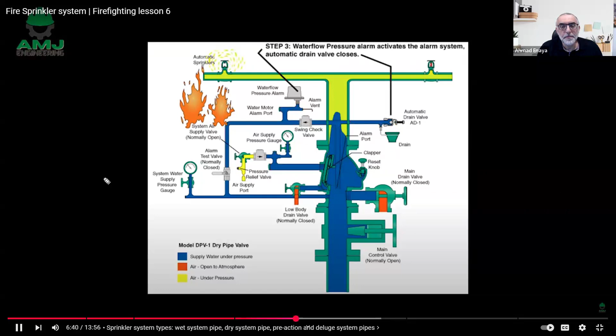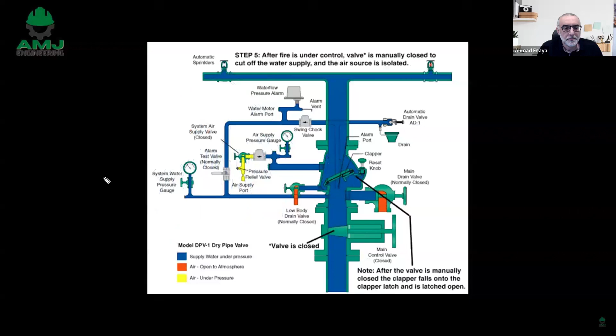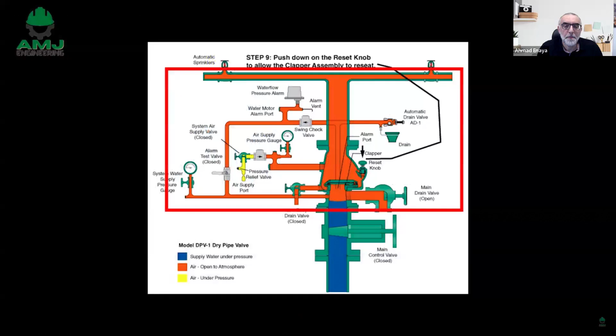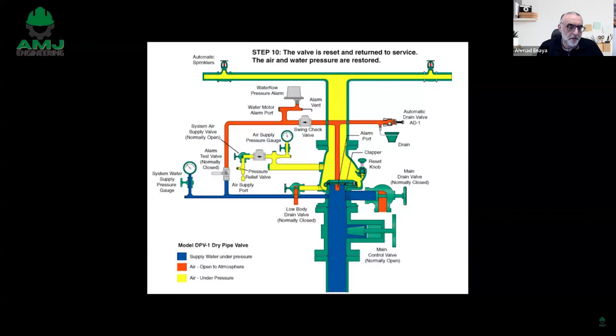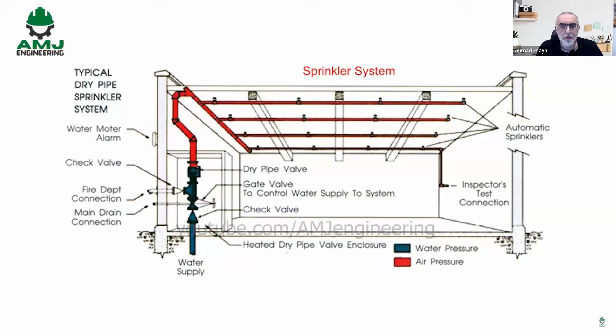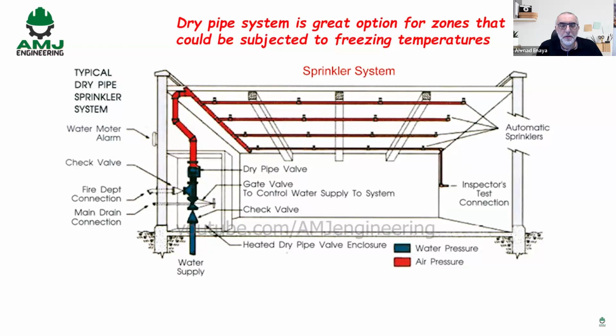Air is released from the now open sprinkler head. This creates a drop in pressure, causing the dry pipe valve to open and water to fill the system. Water will then flow from the open sprinkler head. Since there is a delay between sprinkler operation and water flow, the size of dry pipe systems is limited. The size limitation is intended to minimize the amount of time water delivery is delayed. A dry pipe system is a great option for unconditioned spaces or locations where the temperature of the space cannot be guaranteed to be high enough to prevent water in the system from freezing.